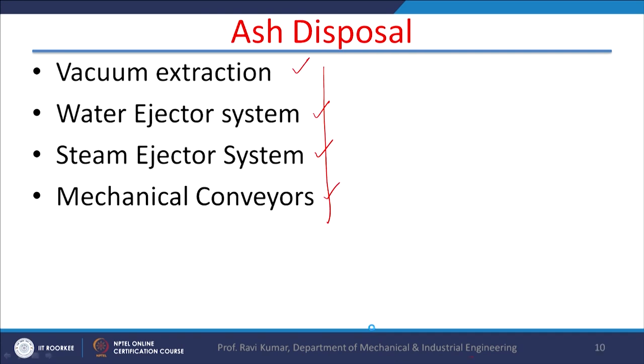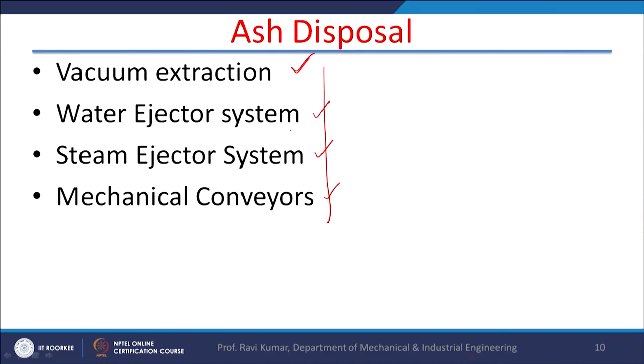Regarding ash disposal methods: vacuum extraction is done through vacuum but it consumes high energy. In the water ejector system, the principle is that high velocity fluid flows over a surface, creating low pressure due to the Bernoulli effect, which causes movement of the fluid or solid from the bottom upward. The working fluid can be water or steam.